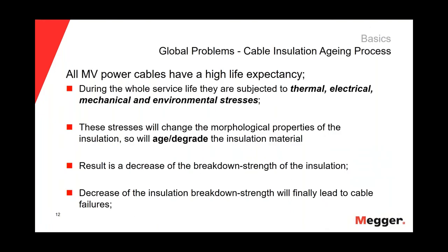To understand the aging process of the cable, we need to understand that today all medium voltage power cables have a high life expectancy — around 50 years. But during the whole service life, they are subject to thermal, electrical, mechanical, and environmental stresses. These stresses will change the morphological properties of the insulation, aging and degrading the insulation material. The result is a decrease of the breakdown strength of the insulation, which will finally lead to cable failures.